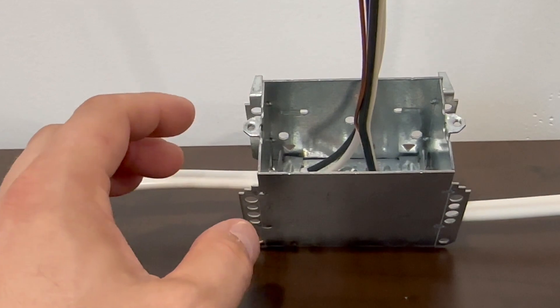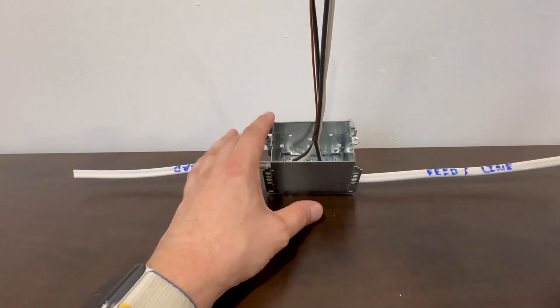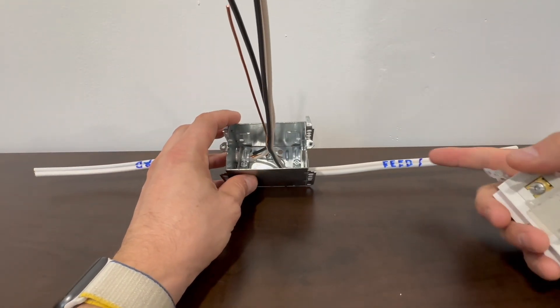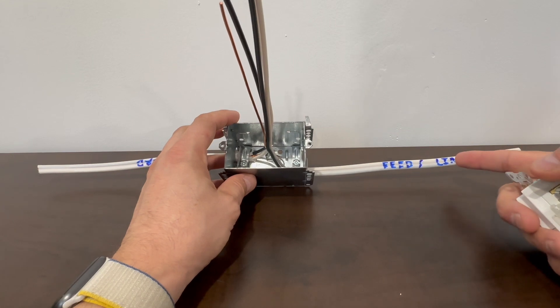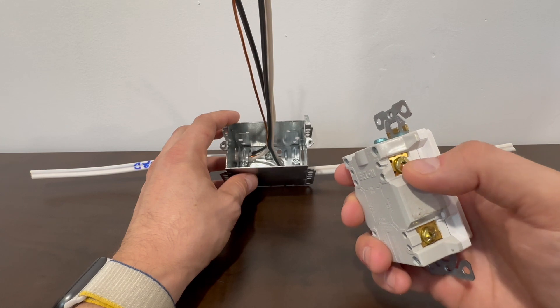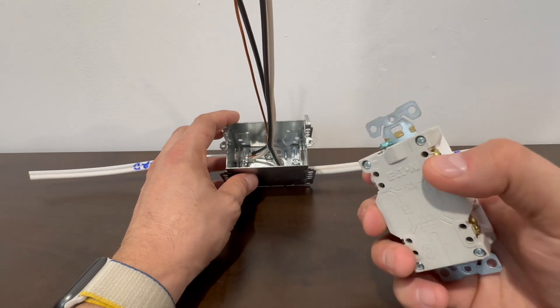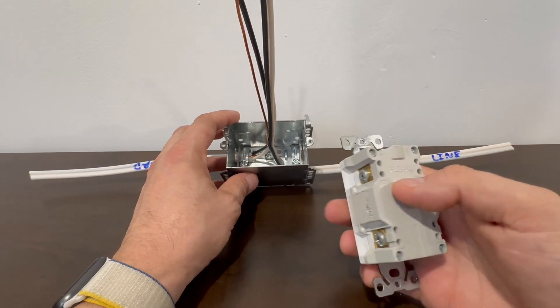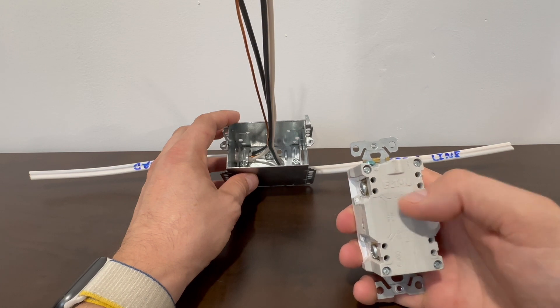Again, what that means is when you're looking at your receptacle and how you're going to tie it in, your feed is on your line side. That would go on the line side of the breaker up here. So there would be your brass screw. That would be where your black wire goes of your feed. There's your silver screw. That would be where the white wire goes of the feed.